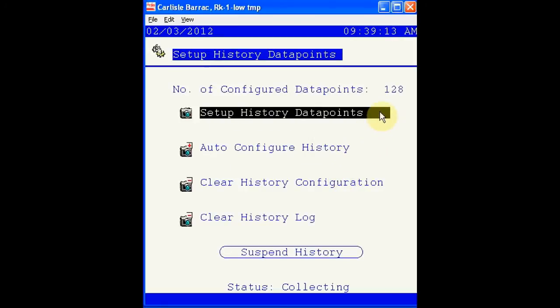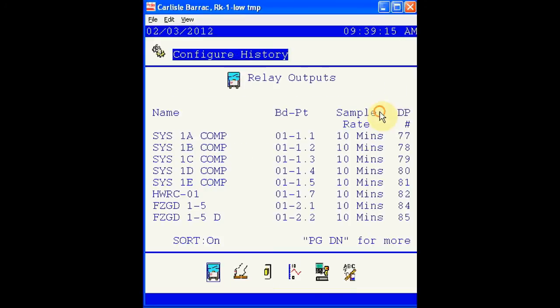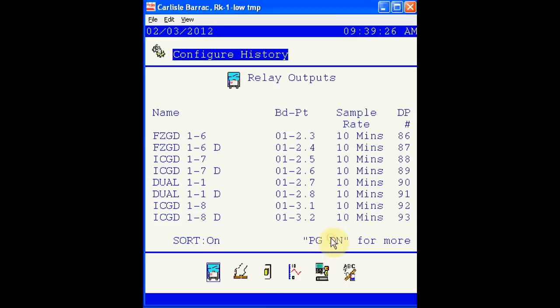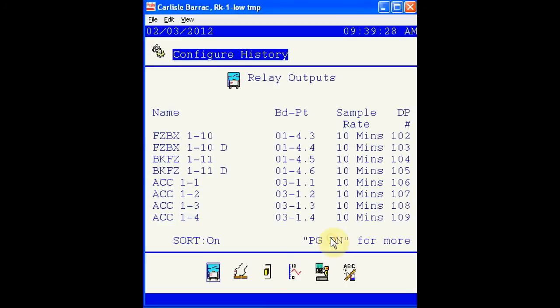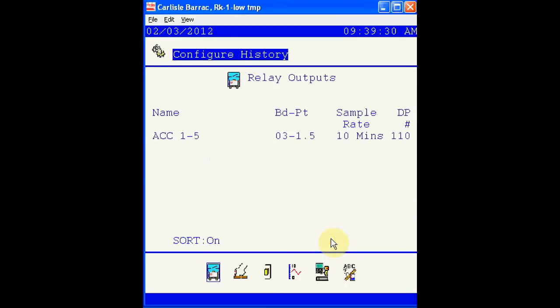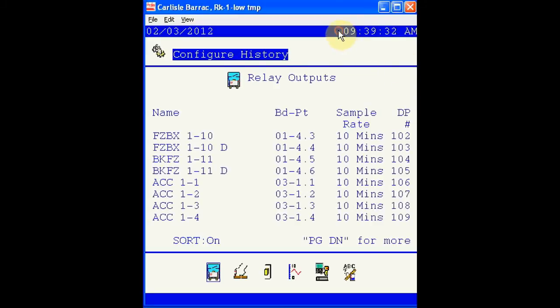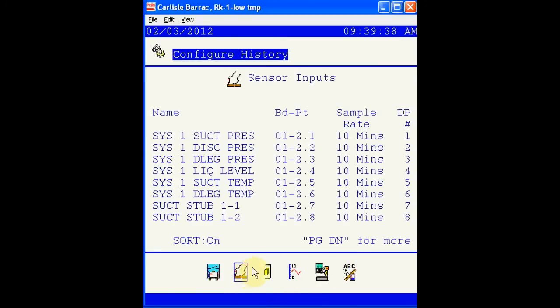Then set up history data points. Here you can see a listing of all points. The sample rate in this case is set to 10 minutes for each point. If we page down through the relays, we'll be given a display of each point, and we can see if there are any points that are not being logged in history.